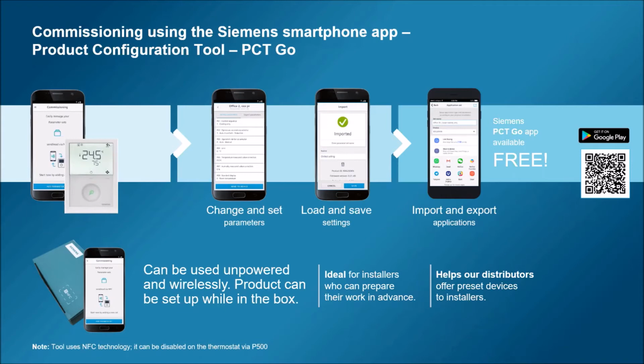You can also start from a new setting, change the parameter, change the application, change the screen parameter, for example, and send the values and all the settings into the thermostat by approaching your smartphone to the thermostat. It's super fast. And as soon as it is done, the thermostat is working, it's preset. You can also copy these settings and download them to 10, 20, 100, 1,000 thermostats. If they're all set the same way, you can really do a commissioning in a very fast and efficient way.